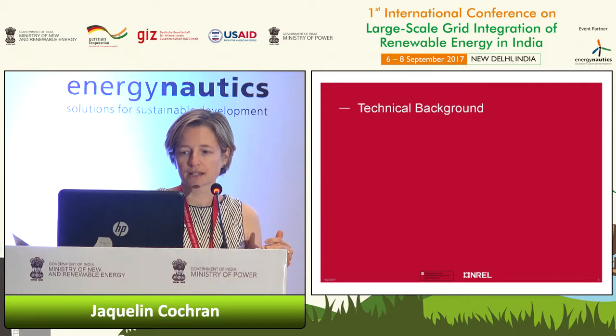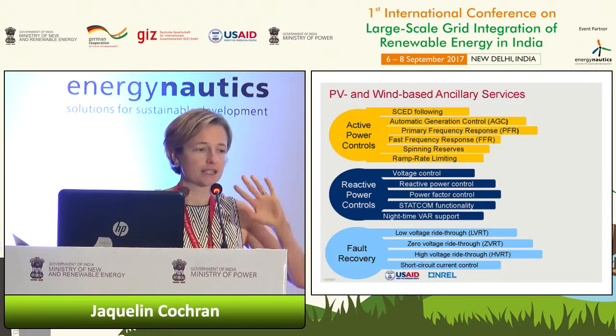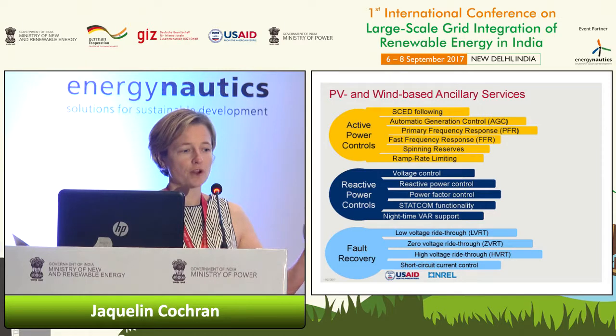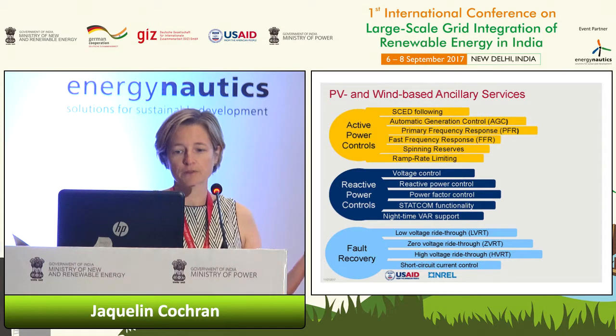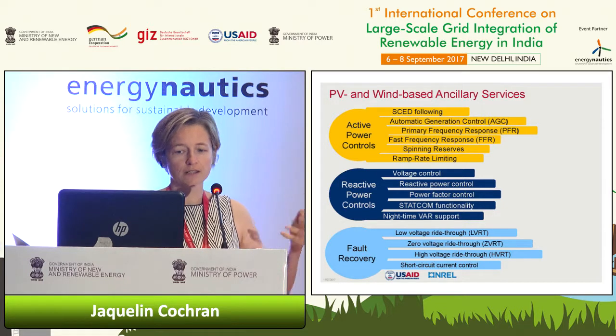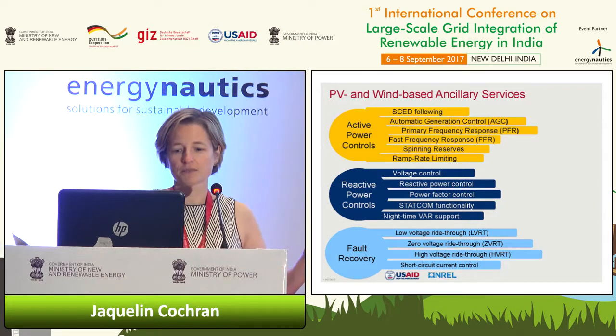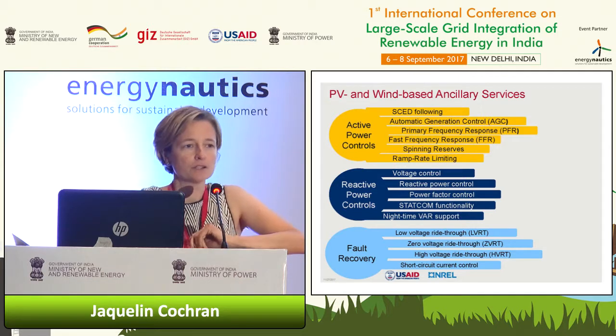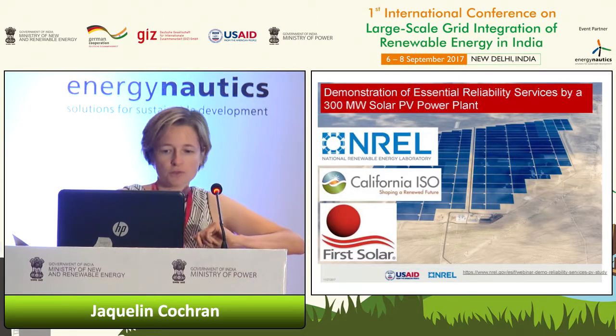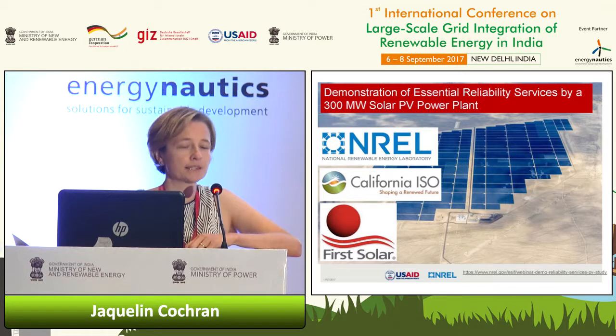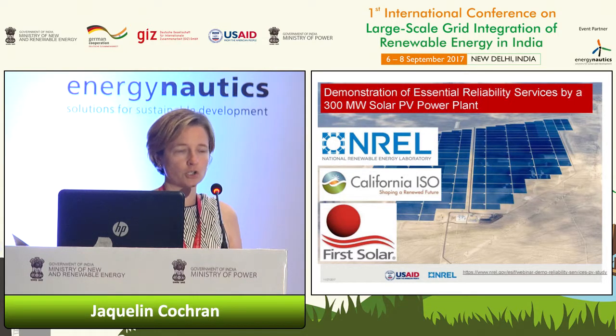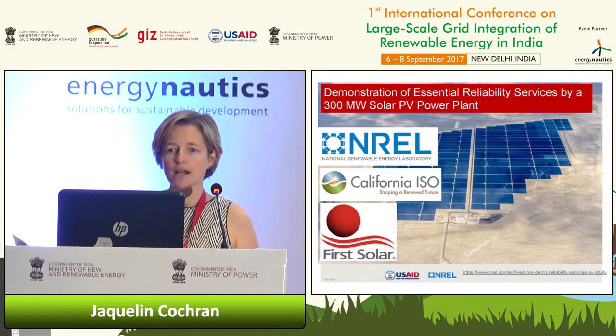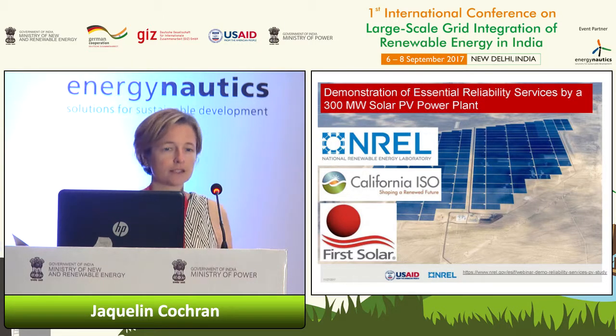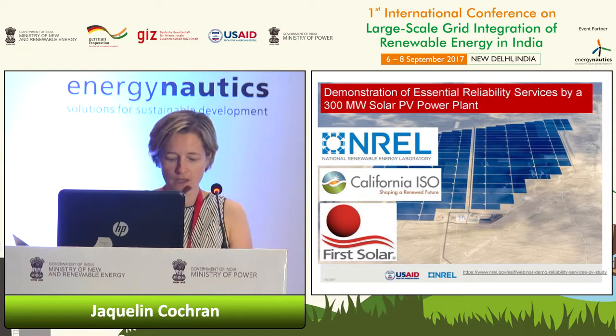So first, the technical background. This is just a summary of all the services that wind and PV can provide: active power controls, reactive power controls, fault recovery. I'm not going to go through the list because we've already heard a bit about this. But I will pause and go through this recent report that NREL did with Cal ISO and First Solar, looking at what are the reliability services that a 300 megawatt solar PV power plant can provide. This power plant is located in California.